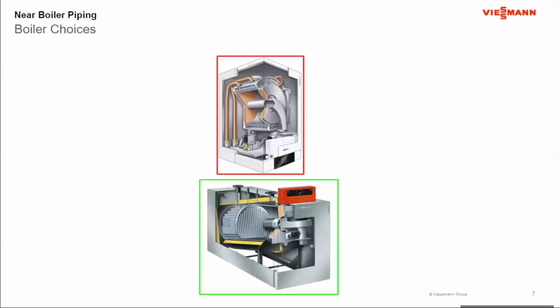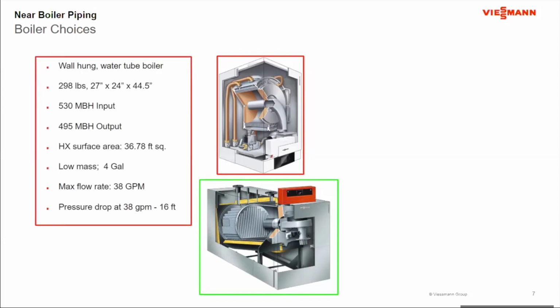Okay. So when we look at boiler choices, they really come down to 2 styles of boilers. We'll call them water tube boilers and fire tube boilers, okay? And each one represents different design criteria that bring together a different package, if you will. So let's start with the wall-hung boiler. Wall-hung boilers, in most cases, are going to be water tube, particularly when we get into the commercial sizes. And from an aspect of what I do, I tend to deal more on the commercial side of things than on the residential.